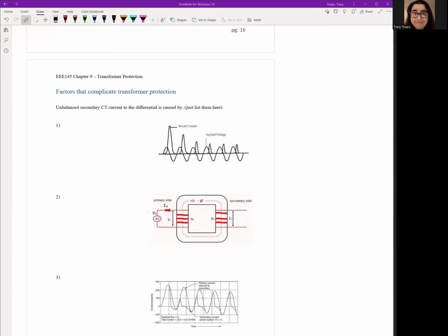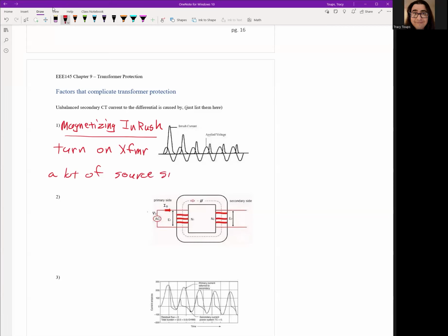The three big ones we're going to see, the first one is called magnetizing inrush. Basically, when a transformer turns on, so you turn on a transformer from an inert dead state, you'll have a lot of source side current. And this is to magnetize the coils. So remember, a transformer is nothing but a giant inductor. And whenever the inductor is dead, you need to send current in to energize the magnetic field for the transformer. So that's that inrush of current, which is only from the source side.